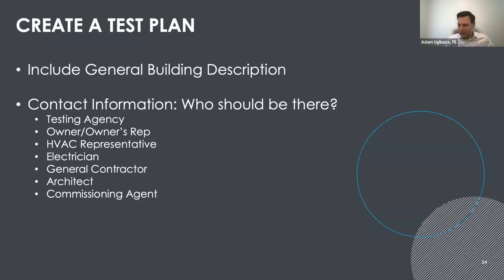So contact information, then we're going to dive in a little deeper to that test plan. So testing agency, owner's rep, HVAC representative, very key. They installed the systems, they understand them. It's very critical that they are part of that process because they're the most knowledgeable with those systems. Electrician, that goes to understanding your circuits to power the fans. You don't want to be stuck in the middle of the night with a blown breaker and you can't get to the electrical panel, or understand where an independent circuit is. Typically you can get your hands on some electrical plans from the electrician early on. They may not necessarily need to be there the day of the test, but it's important that they're involved with the process. General contractor, absolutely key to the coordination of all of this.